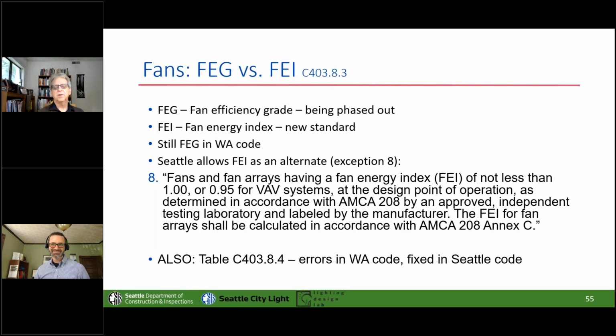So fans, the industry is changing from this fan efficiency grade, FEG, to this fan energy index, FEI, maddeningly similar acronyms, but we couldn't see enough products as we were doing this code to move away from FEG quite yet. And so in Seattle, we dealt with it. I spent some while working with industry by giving an alternate, so that if the fan you're getting only comes with an FEI rating and not an FEG rating, you can use the FEI instead, and that'll get us through, at least in Seattle. That will allow you to use either one. If you're outside of Seattle, you might have to go and talk to your code official to make sure that they understand how this works, or just show them the Seattle amendment and see if they like that.